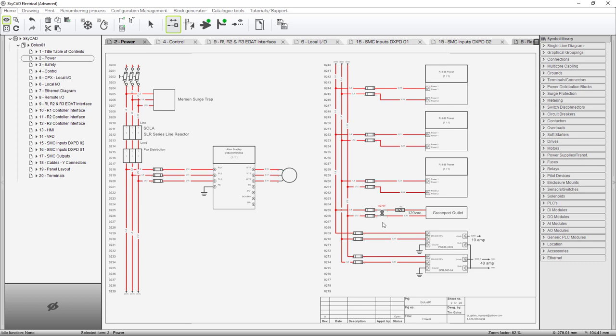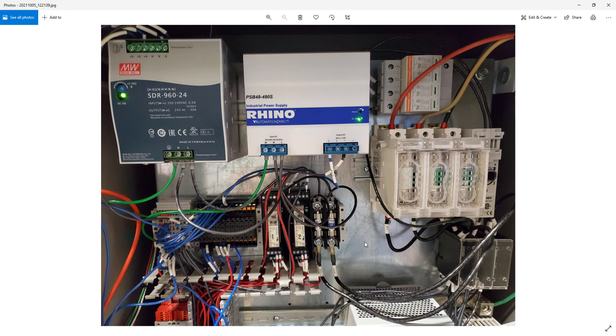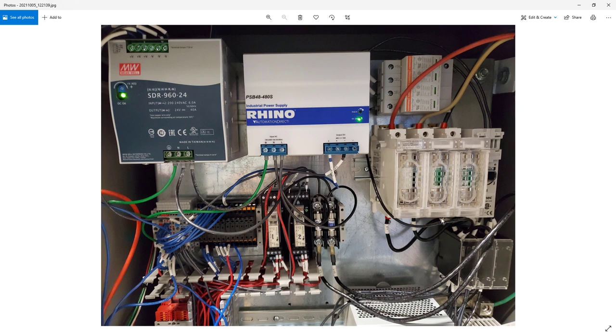Other than that everything on this drawing is 208 to 240 single phase or three phase. And we have the Mersen surge trap and I can bring up a picture of that in the panel. Now if you've watched the other videos you'll remember that there was a transformer right here. That transformer has now been moved up onto the top of this enclosure in its own NEMA 1 box. So the three phase power runs from the distribution block down here in the lower right up through and out the top of the enclosure into the NEMA 1 enclosure up there and then the fuses for the transformer are actually up there.